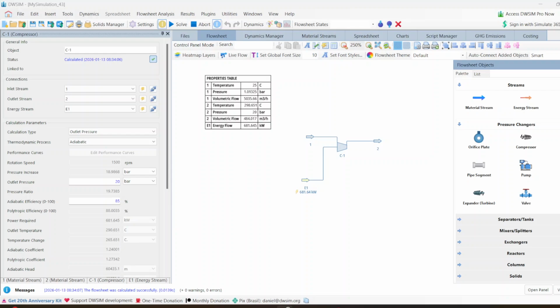So for this we need to use polytropic efficiencies, or whichever you want to use. My rule of thumb is, if I'm making a very small single stage compressor, I rely on adiabatic isentropic compression. But if I'm trying to make a realistic system with multiple compression stages, or the compression ratio is very high, then I use polytropic efficiency.